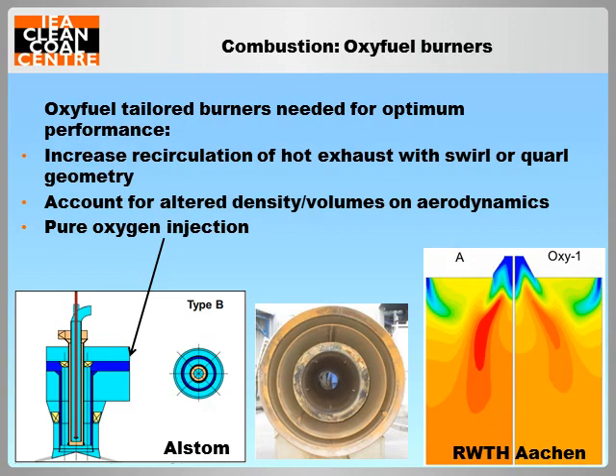However, fully optimised combustion performance requires tailor-made oxy-fuel burners, of which numerous examples are now being produced by manufacturers. These generally aim to promote ignition close to the burner either by injection of pure oxygen through oxygen lances or encouraging recirculation of hot exhaust through swirl or quarl geometries. Aerodynamic effects for the burner need to take into account gas densities and volumes which are significantly altered from air-firing.